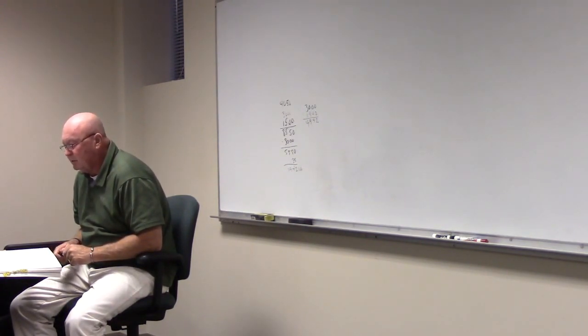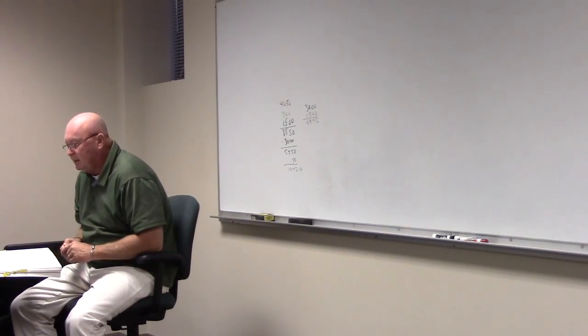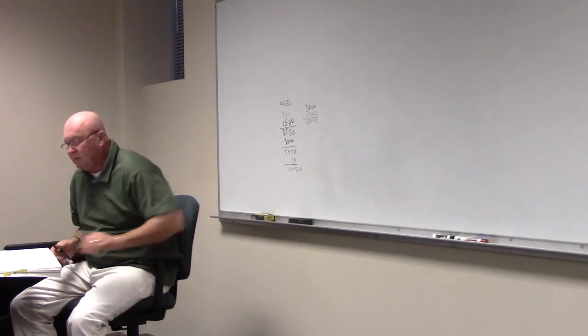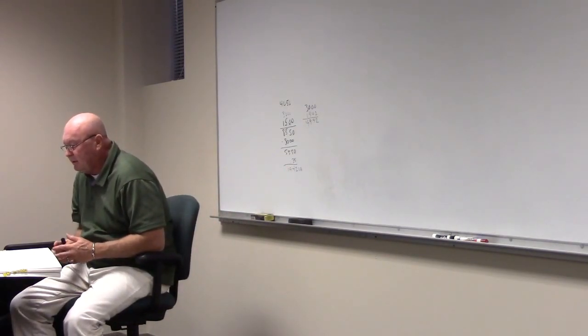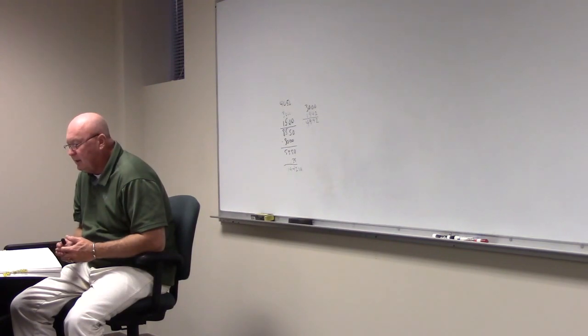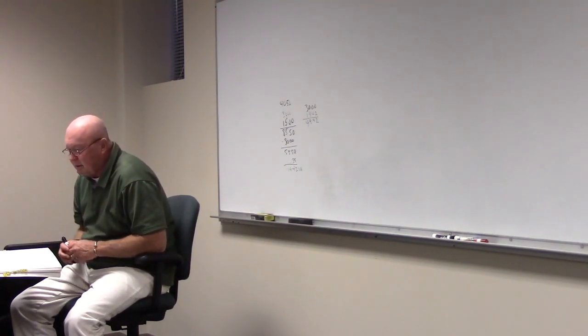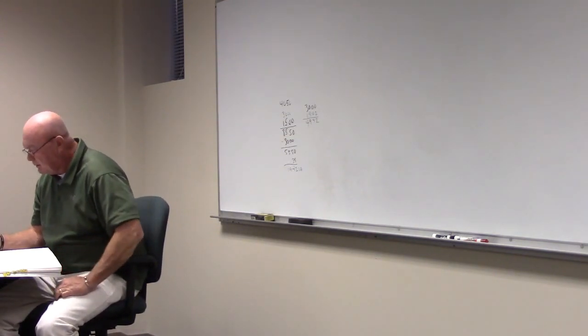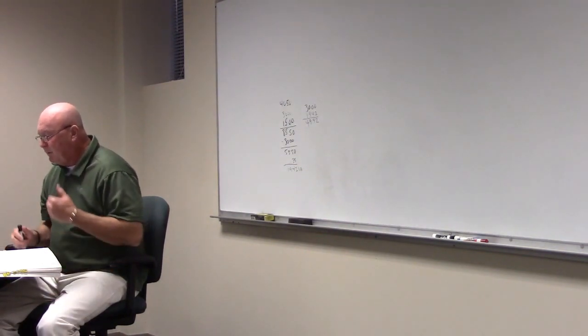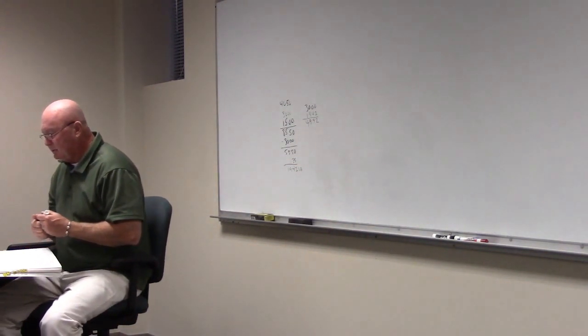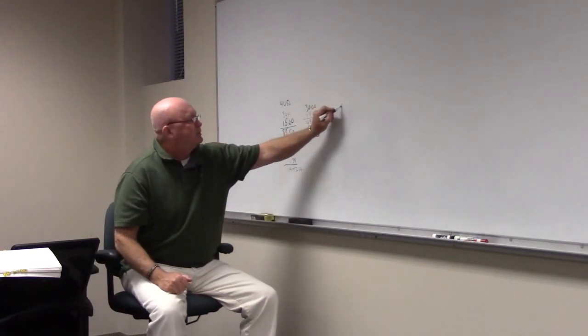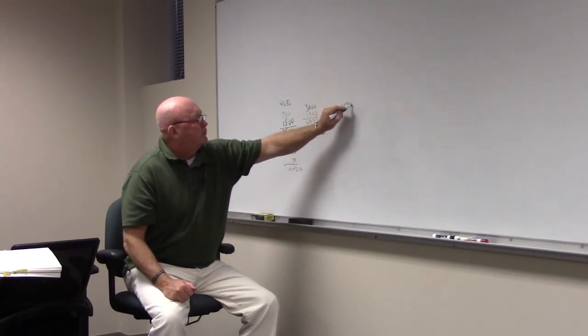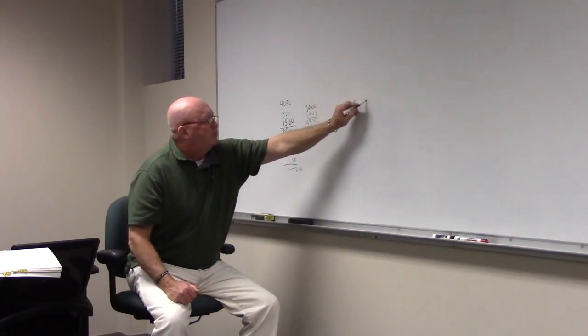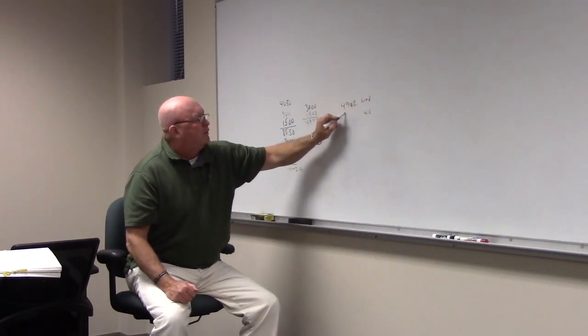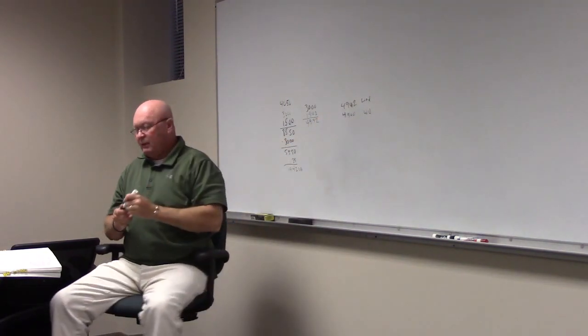What we have so far is in connection with the book, that's what it says. Step number 10 says calculate the load for other appliances. So we're going to leave that to the side, such as a water heater, disposal, dishwasher, furnace. The water heater, what did it tell us it was in the example? Yeah, it says the water heater was 4.5 kVA, which is how much? 4,500. Yeah, so let's just put this down off to the side. Now we have a water heater. This is load. Water heater, 4,500. Let's read and see what it says to do next.